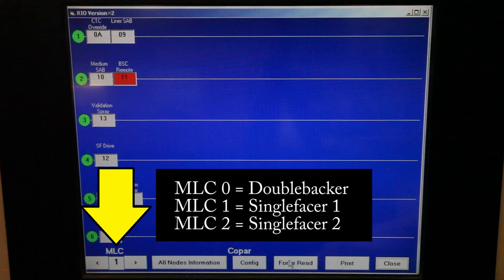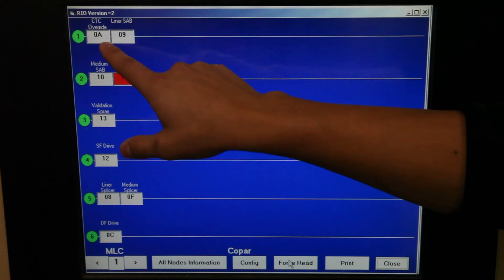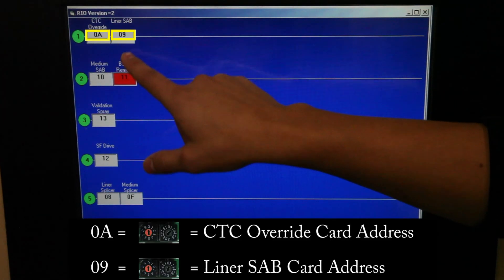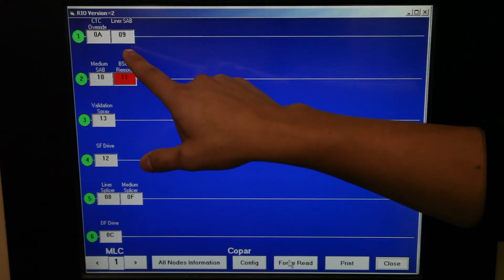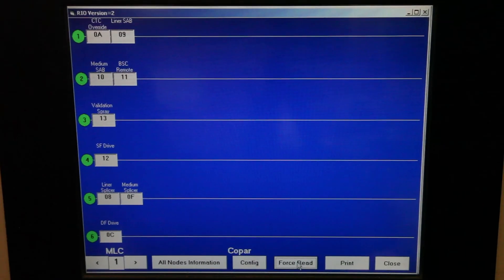Here we are looking at MLC 1. Channel 1 has two cards connected, CTC Override and Liner SAB cards. The value inside each box is the correct address for each card. The values in these boxes do not change. You can use this screen as a reference to verify the address switches on a card are set correctly. As you can see, we have an error on channel 2. That's the BSC remote. This is an indication that there may be a problem on channel 2. What we found was that one of the cards had the jumper set wrong.